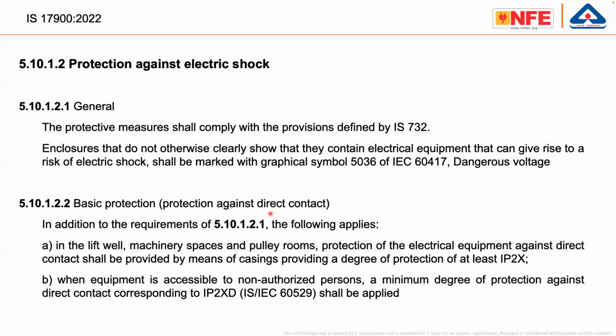Then you can see here, basic protective measures. In addition to the requirement of clause 5.10, that means the above one, the following additional measures are required. For example, in the lift well, machinery space and pulley rooms, protection of electrical equipment against direct contact. That means people shall not touch these electrical appliances. It shall be provided by means of casing having at least IP2 protection. So the second paragraph, we can say that this is an additional protection which has to be made available in the lift well or the lift room and so on. So this is the basic protection.